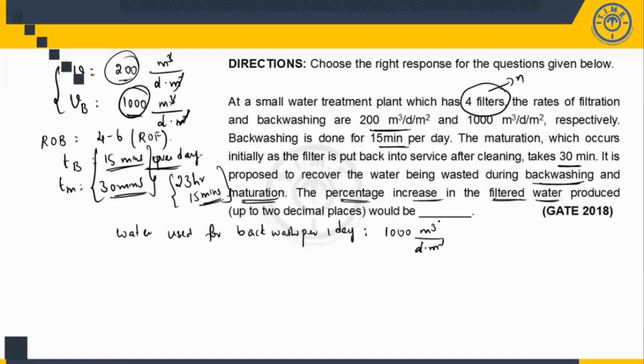Now, for 1 day, it is 1,000 meter cube per day, 1,000 meter cube per 1 meter square of area. But backwash is done for how much time? 15 minutes. 1 day means how many minutes? 24 into 60. For 24 into 60 minutes, it's 1,000. For 15 minutes, it is X. How much is X then? X is 1,000 by 24 into 60, into 15.